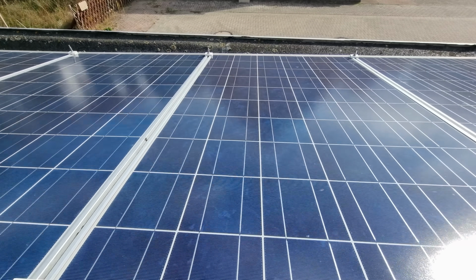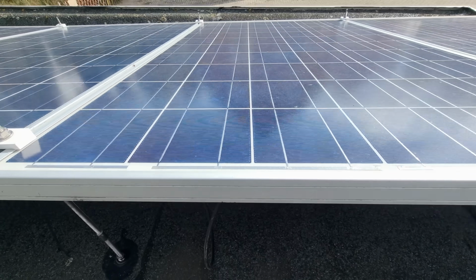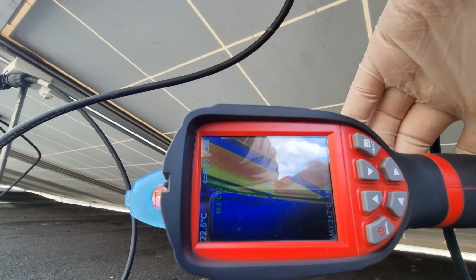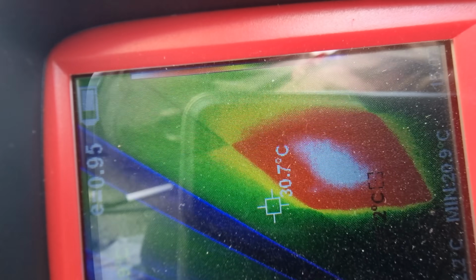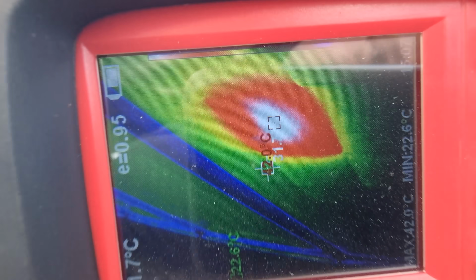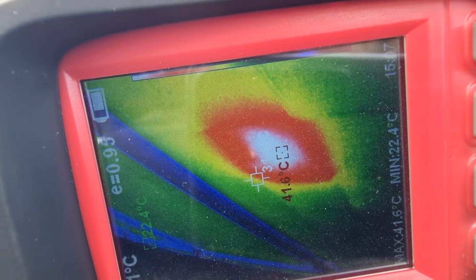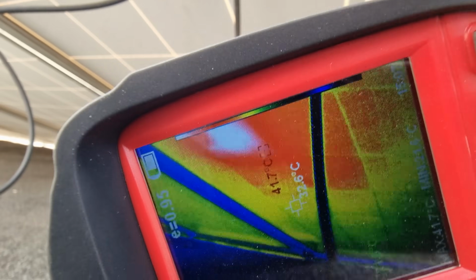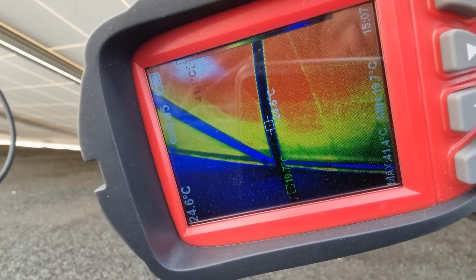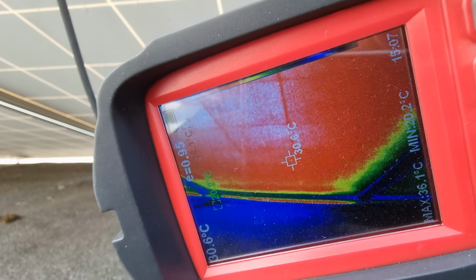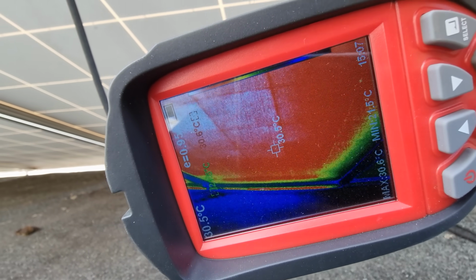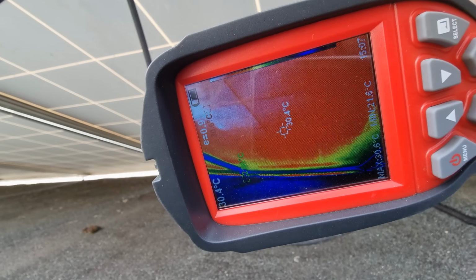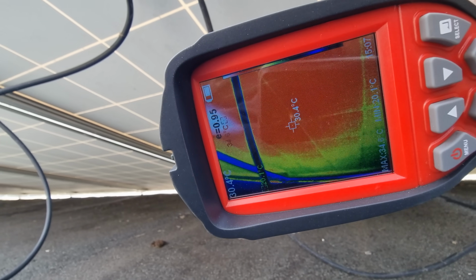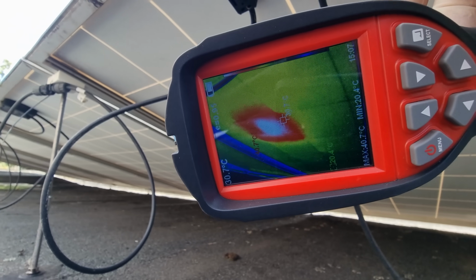In practice, one of my used panels seems to have a bit of a problem here. It's clean and never under any kind of shadow. Yet this one cell constantly seems to be over 10 degrees hotter than any other one. Is that a rare combination of a faulty cell and a broken bypass diode? Whatever the cause, excessive temperatures over longer times degrade cells irreversibly. So since my plans luckily only involve 48 out of 50 panels, I'm just going to replace this one with another module.